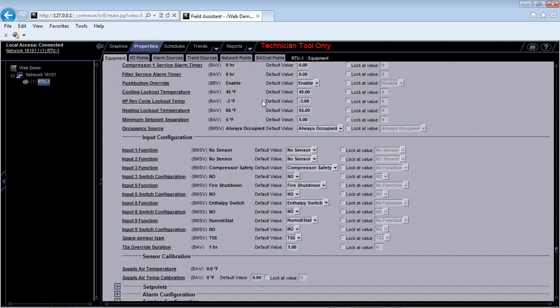Cooling lockout temperature. Right now it sets it up for 45 degrees. On all Carrier rooftops, the compressors have a mechanical lockout at 45. So regardless of what you type in here, if you type 0 degrees outdoor air on this, your compressor is going to lock out mechanically below 45 degrees. But what this value helps you do is if you, for instance, don't want to use mechanical cooling below 50 degrees and you only want to economize, you can set this to 50 degrees and my compressors are never going to come on. I'm only going to use the economizer. Okay? So that's your lockout temperature for cooling.